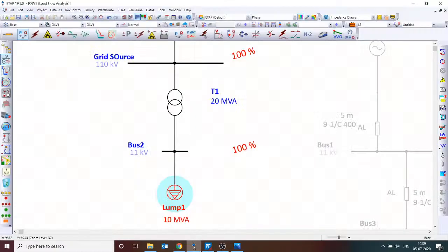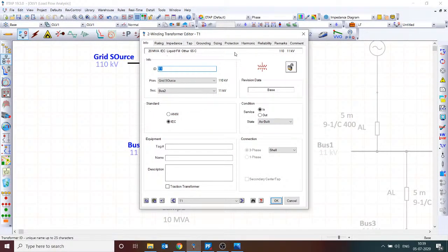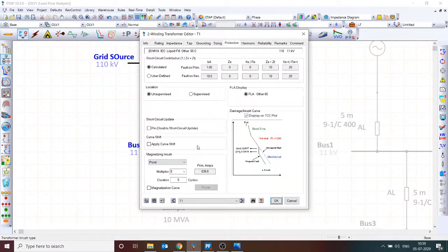Question from Alexander: How is the transformer saturation curve used in ETAP? Transformer saturation doesn't have any meaning in load flow analysis. There is no point in talking about transformer saturation in a load flow context. In ETAP transformer modeling, there is no saturation curve option — only in the protection module is there something relevant. If your question is more specific to transformer energization or CT saturation, please clarify and we will answer it.